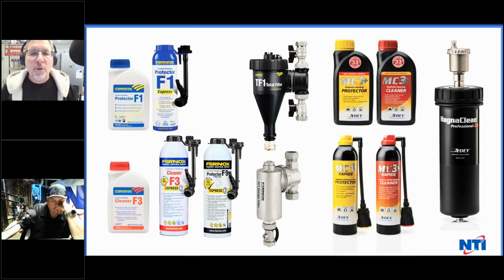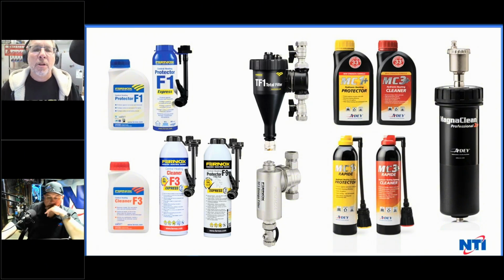What does it mean for you? It means you're coming back every month for the first 6 months, or at least the first and second month, and checking the magnet. If you go in there and the magnet's not packed, then make it 2 months. If the magnet's fully packed, make it every 3 weeks. And you'll see that eventually it'll get less and less, and you can make it an annual service to clean that magnet. All these guys, ADEY, BoilerMag, Fernox, they all have videos online to see their magnetic filters and their crap. So it's all there.